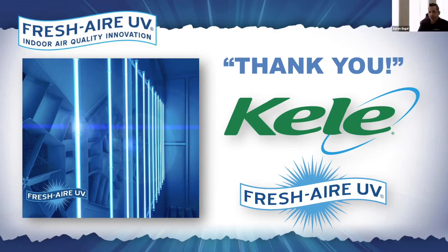They're very forgiving. The lamps have the ability to essentially really stay clean, even in very severe conditions. So, I would monitor the lamp, monitor in the sense that what I didn't discuss is exposure. You never want to expose yourself to any direct line of sight with the ultraviolet light. That's why those interlocks are so important on the door. With that being said, a face shield, protect your eyes and skin, that's it. And you could monitor to make sure the lamp is functioning. As far as cleaning, depending on the application, there really isn't anything required as far as maintaining the lamp.